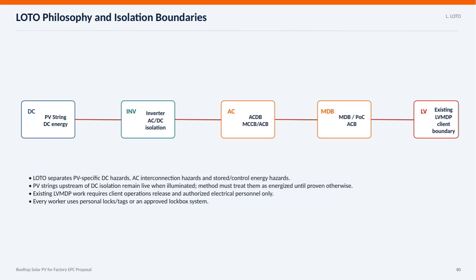Here we're looking at the lockout-tagout philosophy and how isolation boundaries are established, especially in the context of rooftop solar PV systems for factories. The key point is that LOTO separates different types of electrical hazards, specifically DC hazards from the PV strings, AC interconnection hazards, and any stored or control energy hazards. It's important to understand that PV strings upstream of DC isolation stay live as long as they're illuminated, so they have to be treated as energized under all conditions until officially confirmed safe.